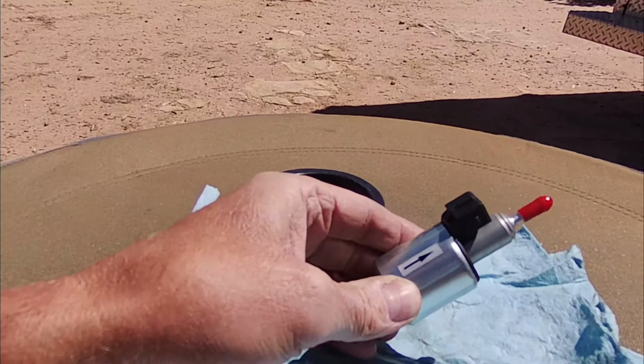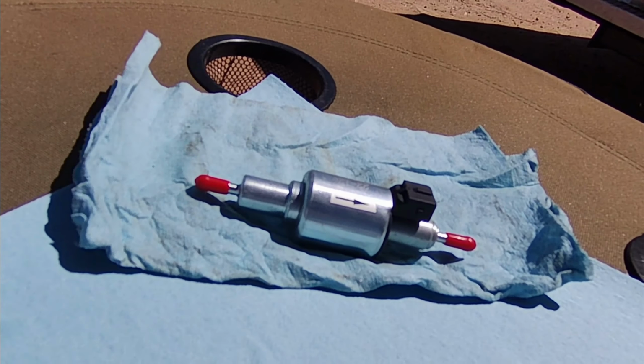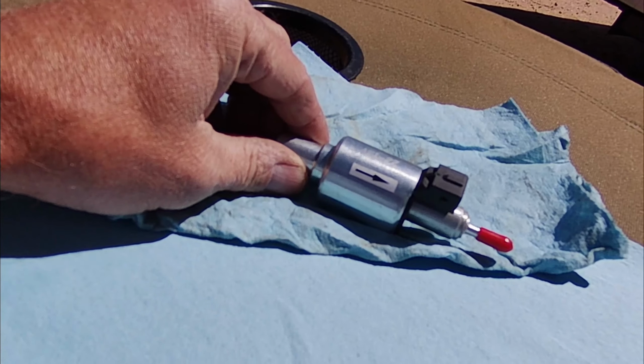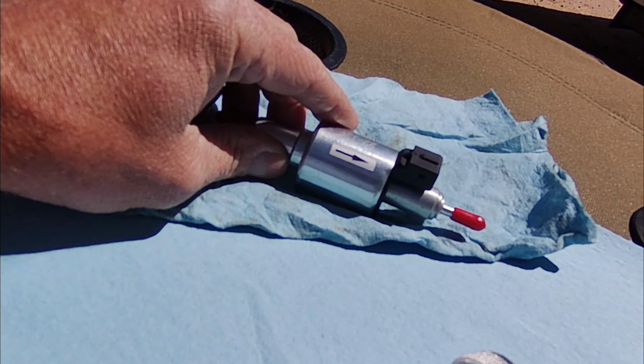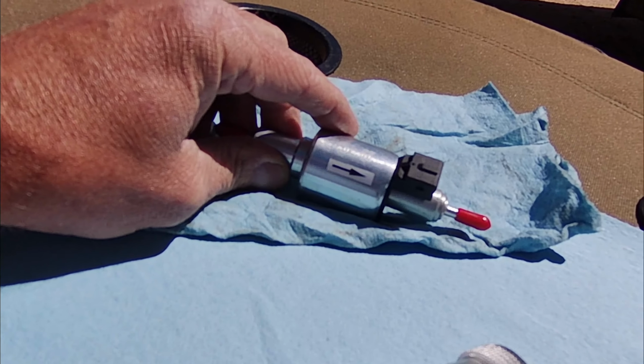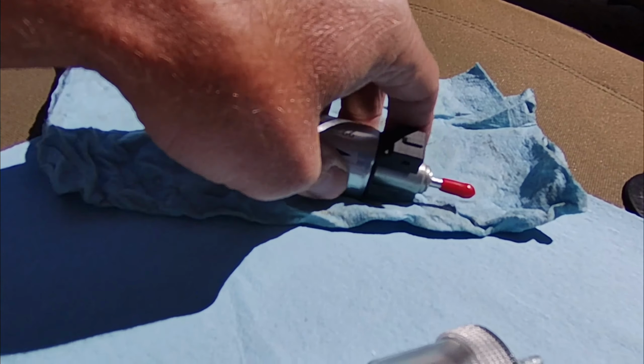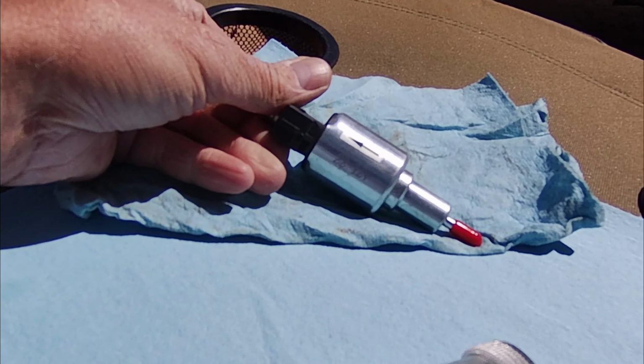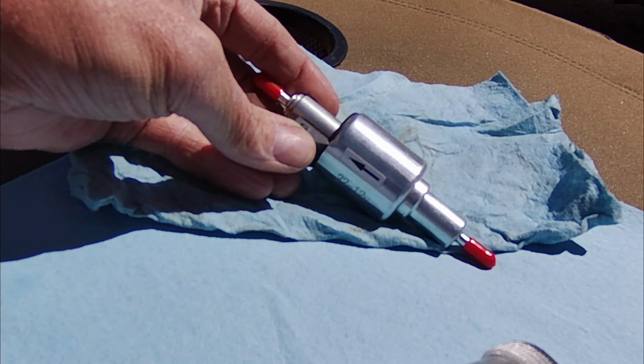Now I want to figure out what caused this pump to go bad. Was it my operation? Was it the fact that I had reduced it down to that 1.2 hertz setting and ran it too low? In other words, did I break this pump, is what I wanted to figure out.